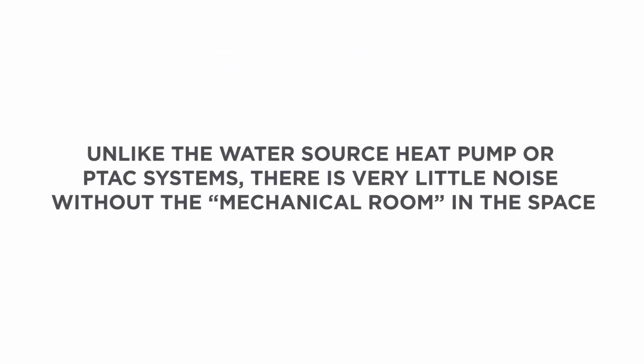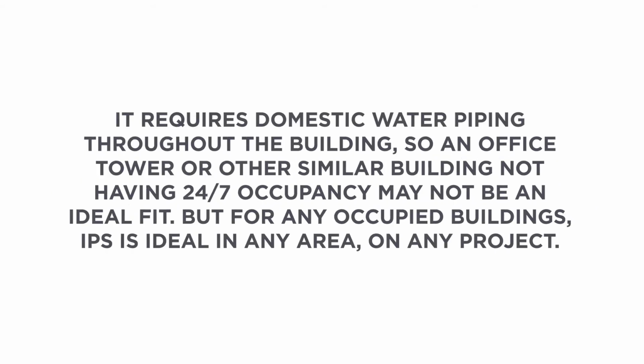And 3, unlike the water source heat pump or PTAC systems, there is very little noise without the mechanical room in the space. The only disadvantage? It requires domestic water piping throughout the building, so an office tower or other similar building not having 24/7 occupancy may not be an ideal fit. But for any occupied buildings, IPS is ideal in any area on any project.